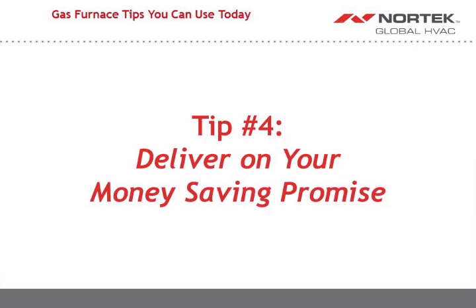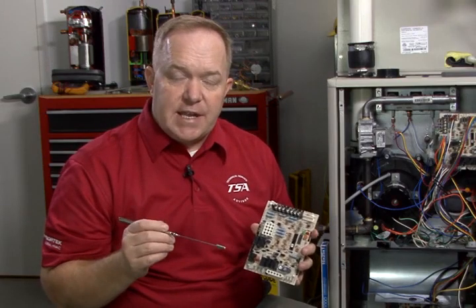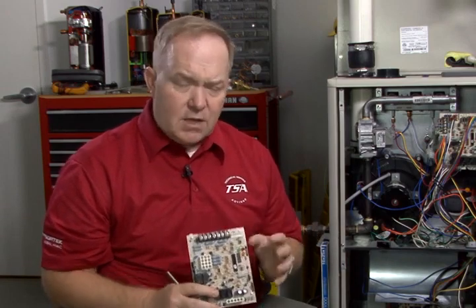Okay, tip number 4. Help the homeowner save the money that you promised them you would. This really particularly pertains to 2-stage high-efficiency gas furnaces. Lots of times with higher efficiency gas heating, particularly if you have multiple stages, those require an additional, upper level of thermostat to be installed, and then you have to set those up properly in terms of their parameters, programming, all that kind of good stuff. The simple fact of the matter, guys, is that very, very often a homeowner may say to you that they will set up the thermostat themselves. It may be that they're waiting for another family member to participate, to set the stat up where they would both want it to be, what have you. And far too often, it never happens.